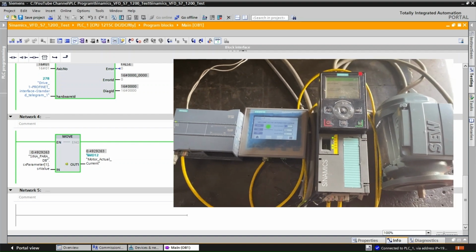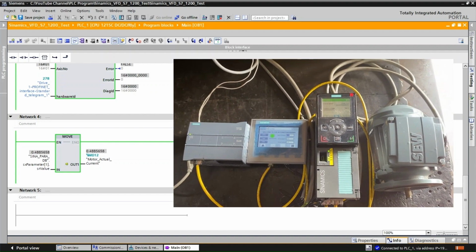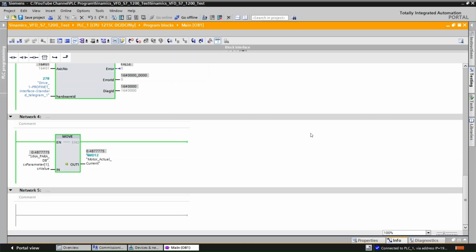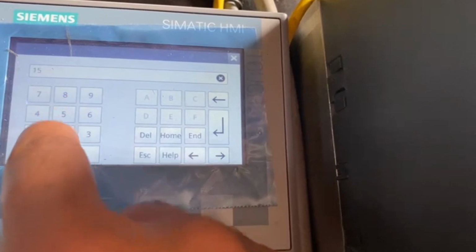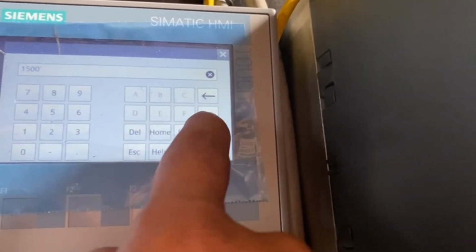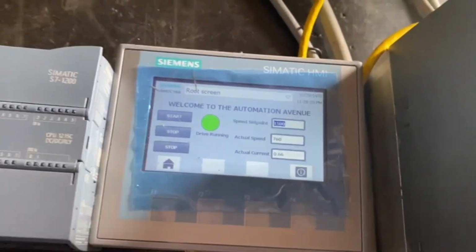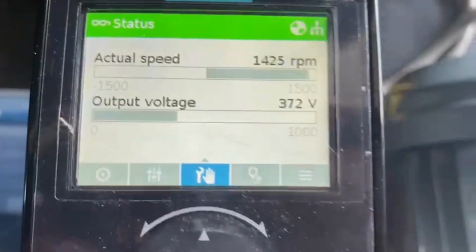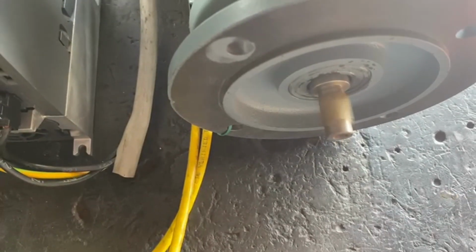This is how you need to do the configuration and commissioning of the PLC and HMI for the VFD. Okay, that's all for now. In this video, we demonstrated how to add a new device and perform the configuration. Then we assigned the IP address to the device, downloaded the configuration to the drive, and commissioned and tested the function. Everything went smoothly.